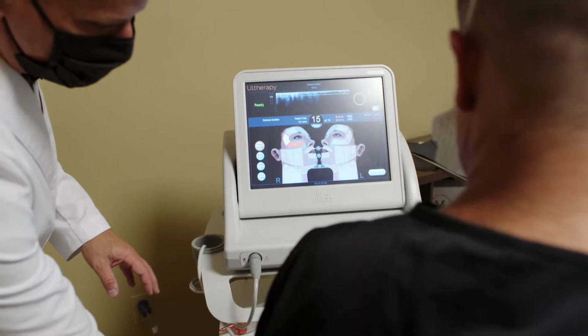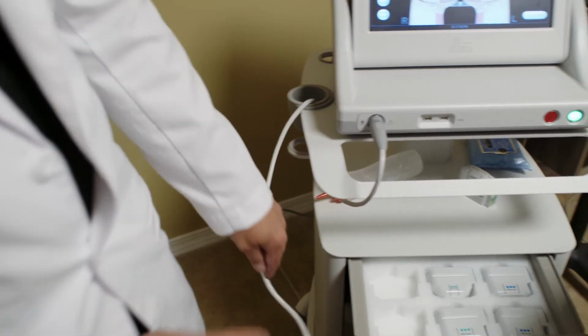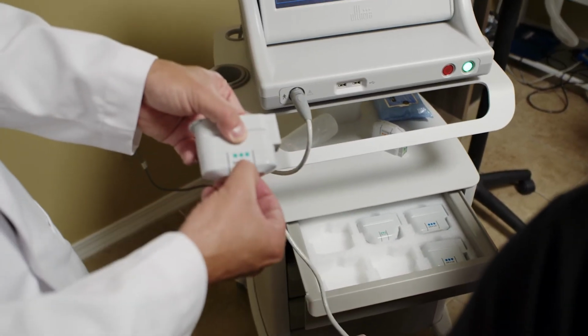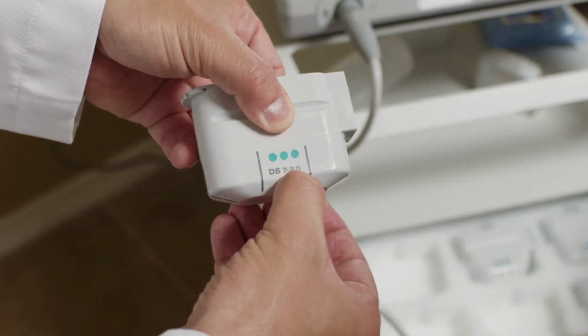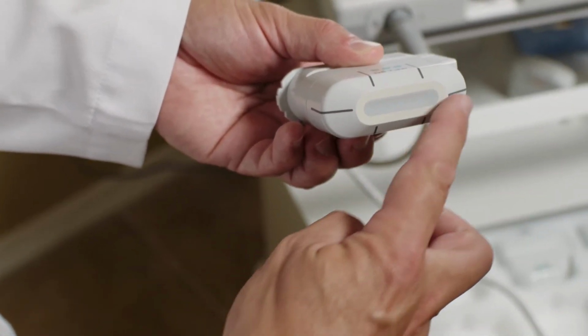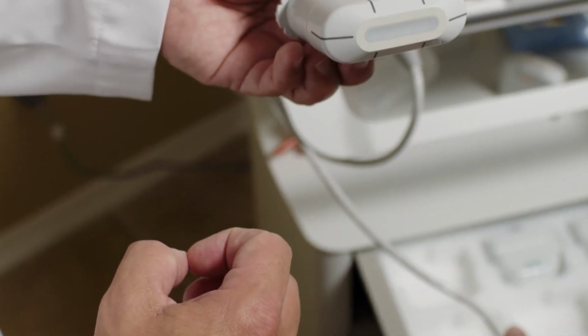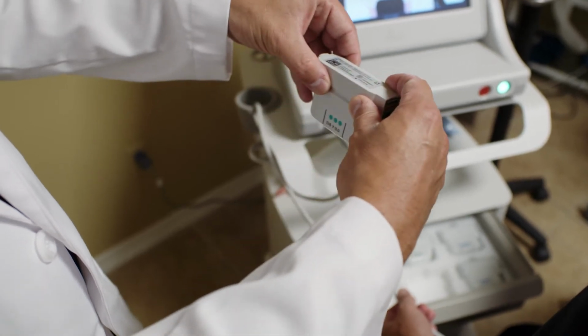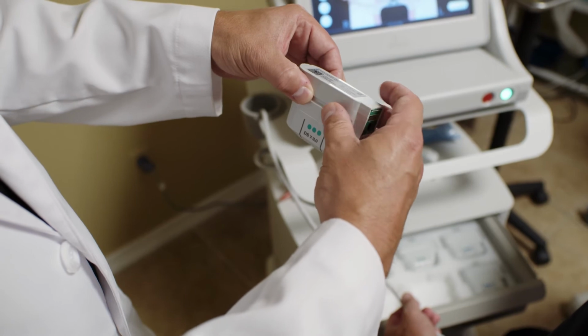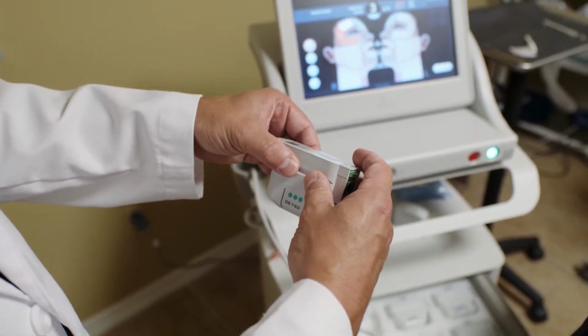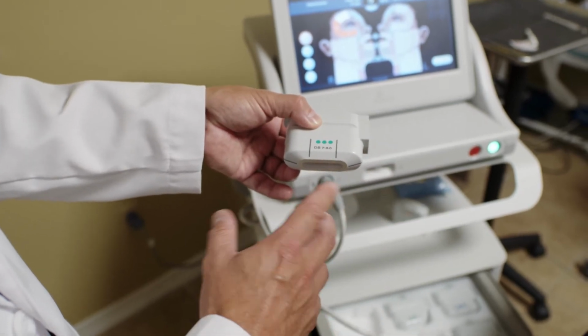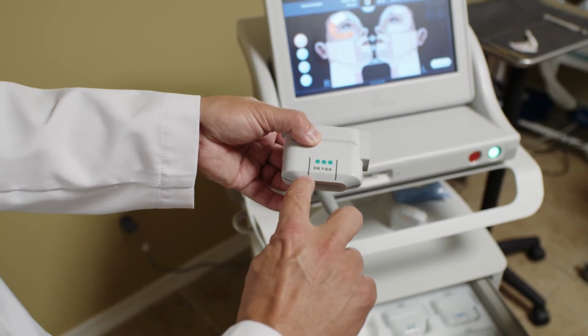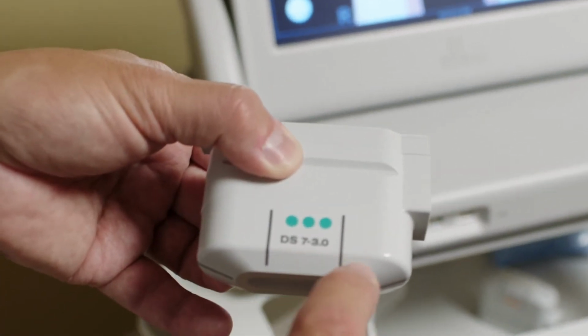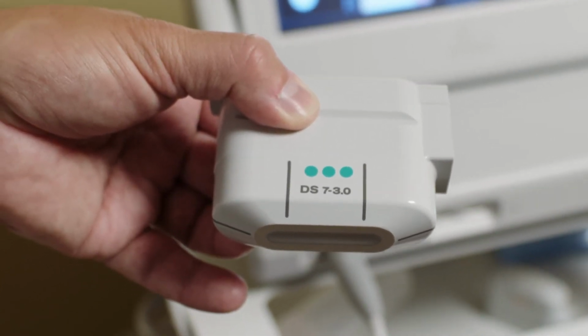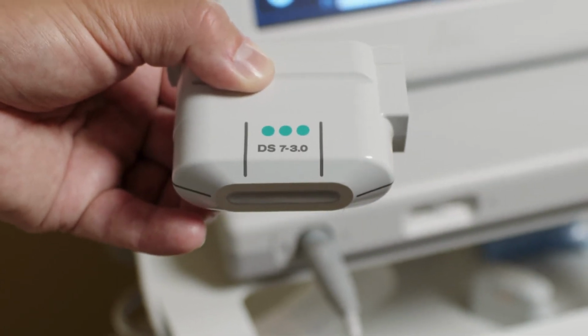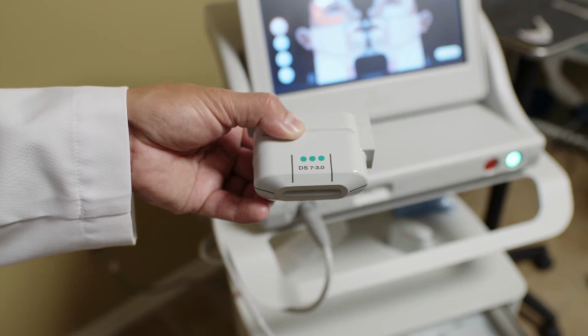As you can see in the cart, there are numerous size heads, and these will show you the different depths. For instance, this is a 3 millimeter depth transducer that we're seeing here. This transducer, we have a conductive gel, an ultrasound gel, that we apply on the patient's face, and then we use the transducer to scan and to see the appropriate depth of treatment, which is usually going to be, for the lower face, targeting the SMAS layer. As we press and discharge the ultrasound, we will deliver energy between these 2 points at 3 millimeters depth for this particular probe. That creates thermal coagulation points, which will create a tissue injury and eventually the healing and collagen production, which is then going to result in lifting.